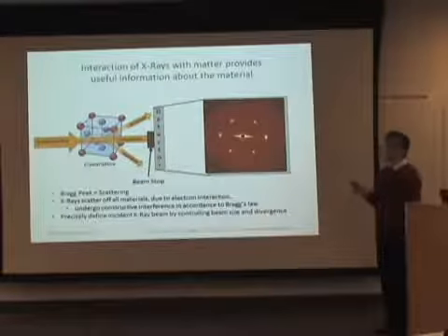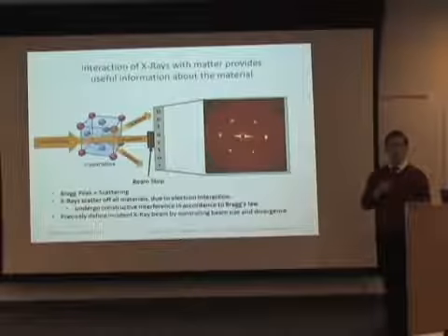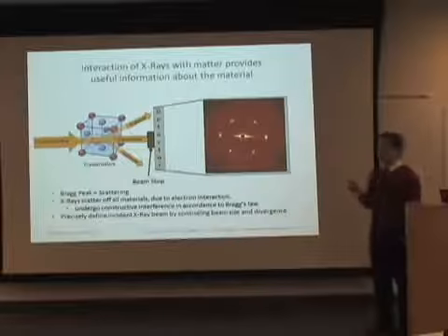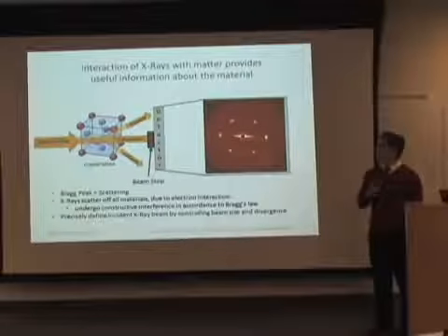The focus of my research this past summer was to precisely define the incident X-ray beam, by controlling the beam size and divergence through blade tuning.